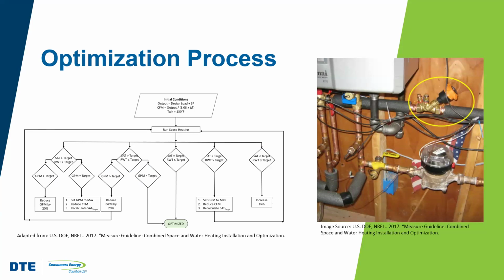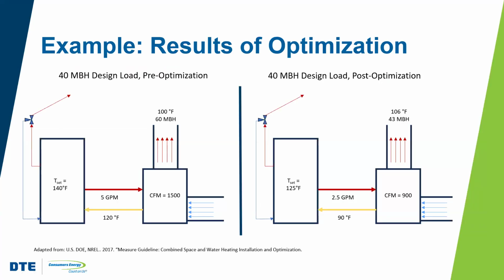This is going to be an iterative process. It's going to involve adjusting the temperature of the water, the water heater set point, the water circulation rate, and the airflow rate, to make sure that you've got all those metrics at their most ideal point for optimal system performance, right? This is just the steps that you might go through for that iterative process. So as an example here, I'm going to go over about 5 minutes, so if you could bear with me, I really appreciate it.